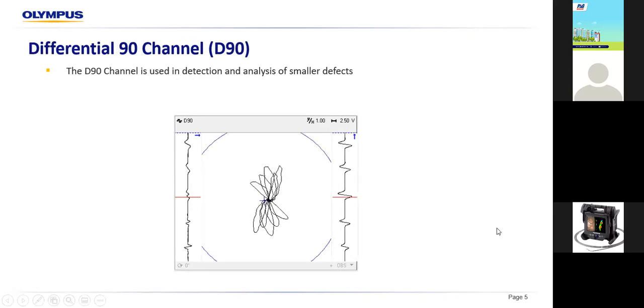So how about differential 90? The differential 90 channel is used to detect and analyze smaller defects. You have your flat bottom holes on your calibration tube, so you'll need the differential 90 channel to analyze those flat bottom holes.